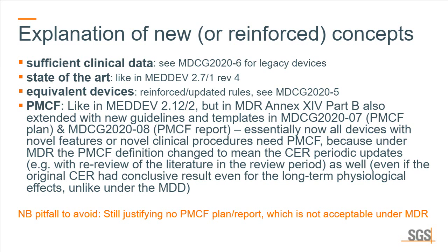When it comes to equivalent devices, there's a reinforced guideline in the MDCG 2020-5, which talks about the conditions under which equivalency can be claimed, and that can give some exemption from having to collect further clinical data.